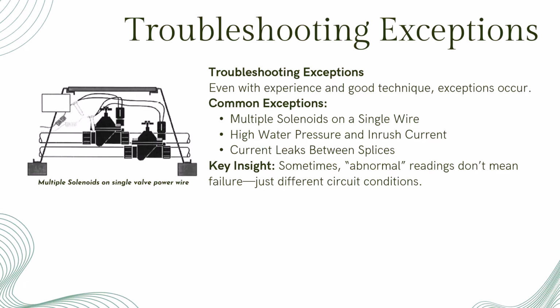No matter how experienced you are, electrical troubleshooting in irrigation systems will always bring surprises. Some conditions don't fit the standard rules, and if you don't recognize them, they can lead to misdiagnosis, wasted time, and unnecessary replacements. The 3 most common exceptions we'll look at are multiple solenoids on one circuit, high water pressure that changes current demand, and current leaks caused by poor waterproofing. Each of these behaves differently on the meter and can easily fool even a seasoned technician.